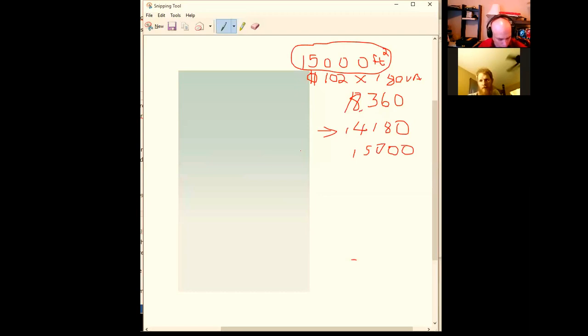So he had showroom questions there, and we covered all those. Then he had a 10,000 square foot office space. He had a 9,800 square foot office space that had receptacles listed there, but you couldn't remember exactly how many there were. But that was the one. You know what? They did give him a square footage on that. It was 50 at 15 amps, and then 20 at 15 amps, and so on and so forth. So there was kind of a breakdown. He's saying he had 9,800 square feet. So in that case, if it's given that way, then I would have taken the 14,180 as the answer, if that's the math on it.